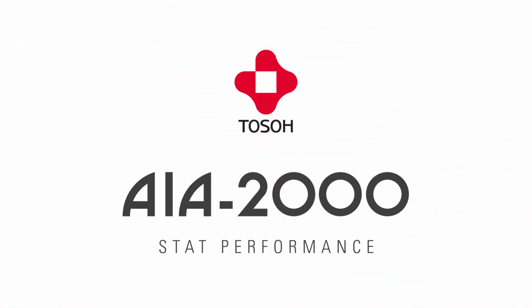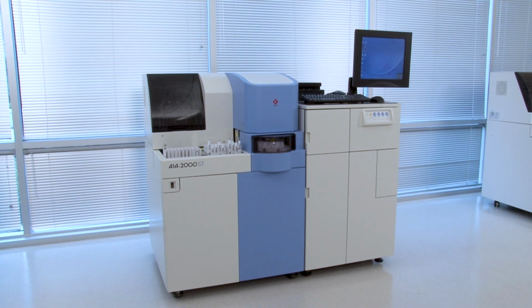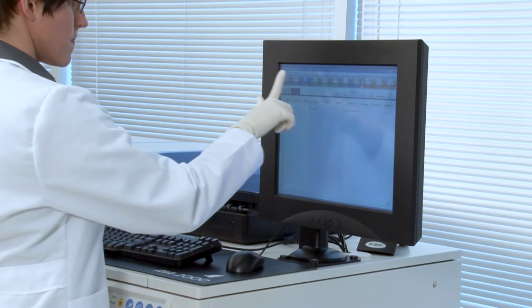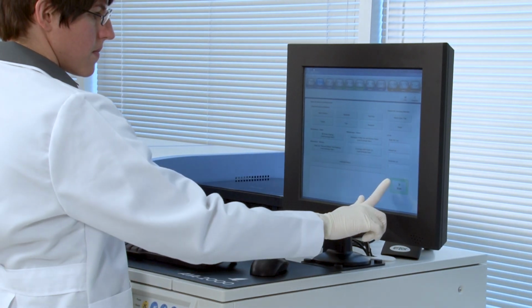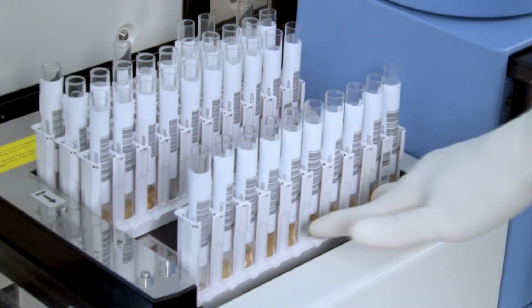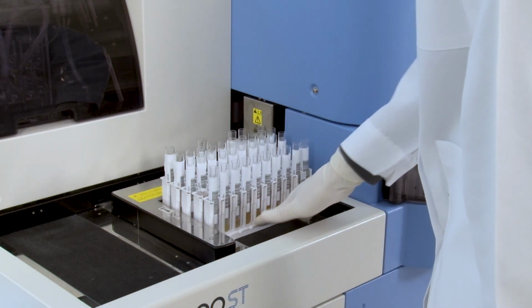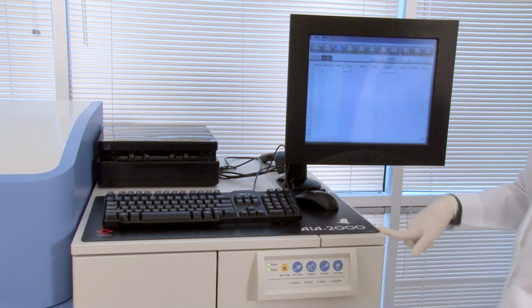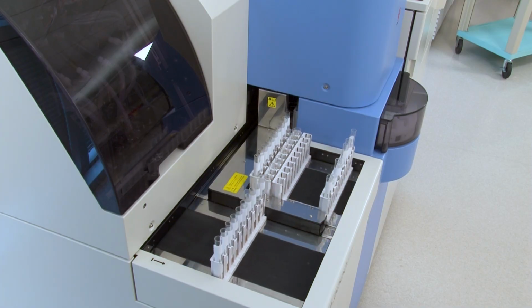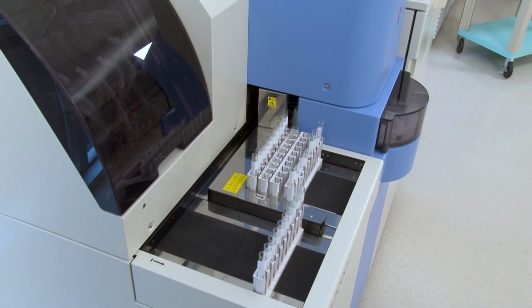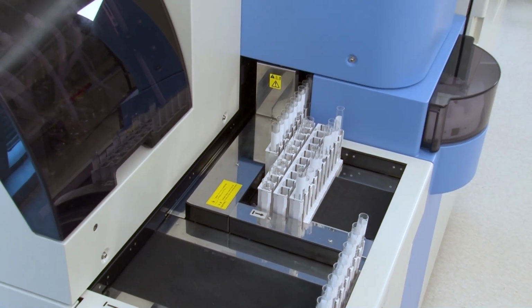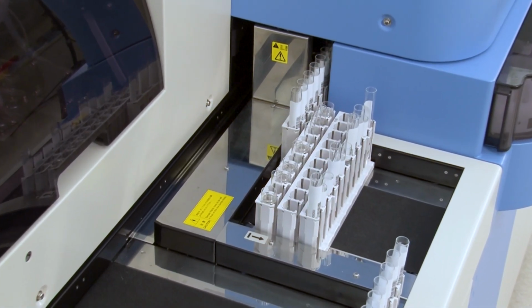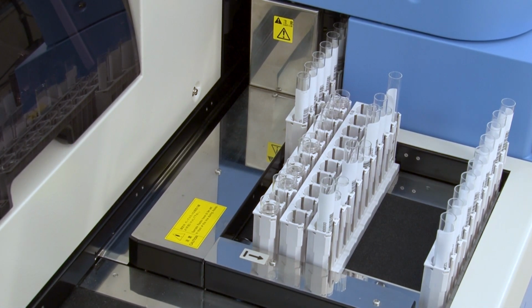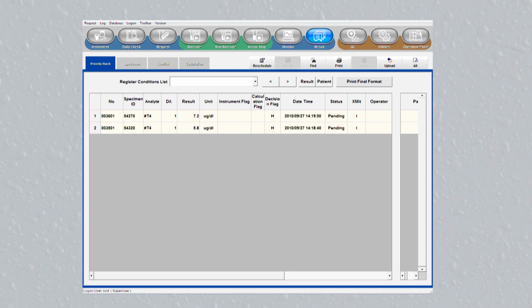Multiple stat processing is available on the AIA 2000. To run a stat test, the operator simply chooses the priority rack option and places the sample rack on the instrument. Stat samples designated on the work list will be processed with highest priority. Once stat samples are processed, routine operation resumes automatically with no intervention from the operator. Stat results are listed in a separate window for easy review.